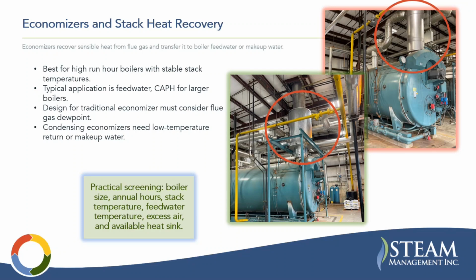Economizers and stack heat recovery. These are best for, I should say they recover sensible heat from flue gas and transfer it to the boiler feed water or makeup water or other process. They're best for high run hour boilers with stable stack temperatures. Typical application is feed water.